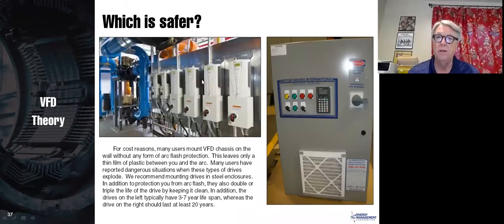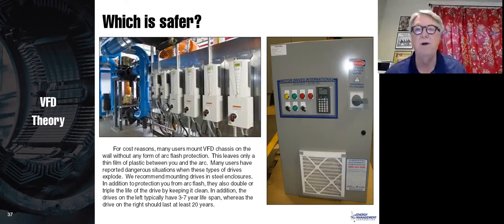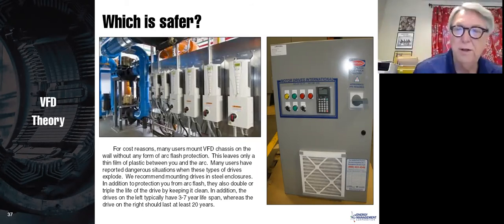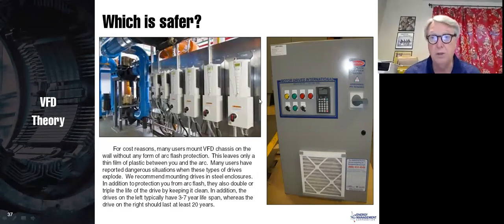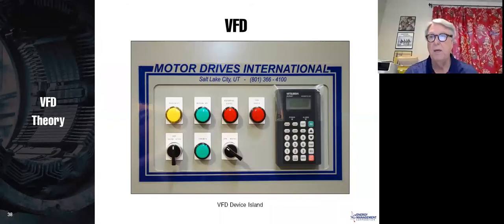Now, a lot of drives are going this way. They're just a drive mounted on the wall. They tend to not have the fans and filters, and they don't have the steel enclosure. They're cheaper and they're smaller. So, of course, those are both big advantages. I really prefer to have the steel enclosure so that you have room to mount things in there, and I believe that it's much better in an arc flash type situation. And the fans and filters. These drives tend to last probably 3 to 7 years, something like that. This drive should easily last 20 years. So even though it takes more space and it's a little more expensive, in the long run, it's probably less expensive.